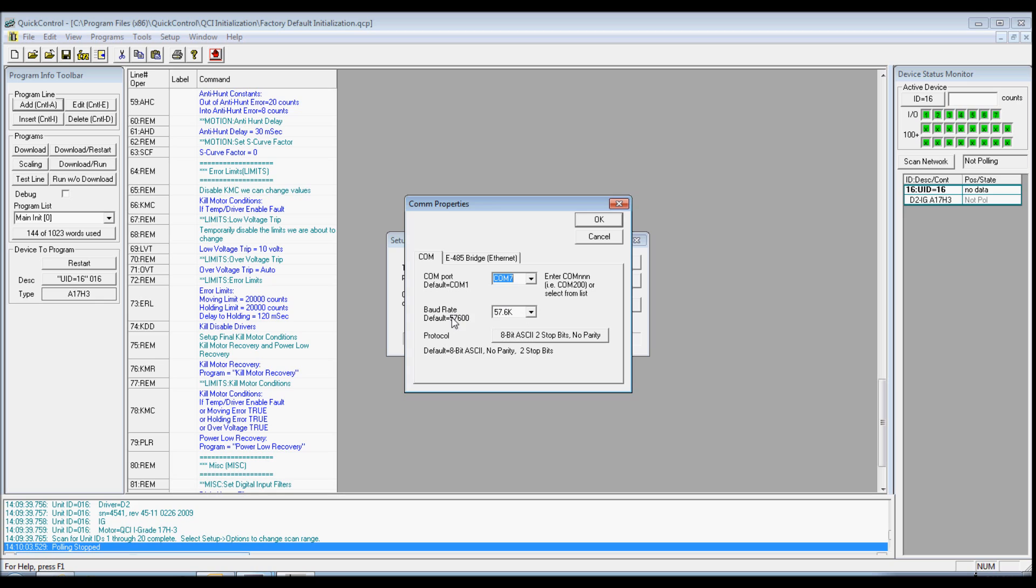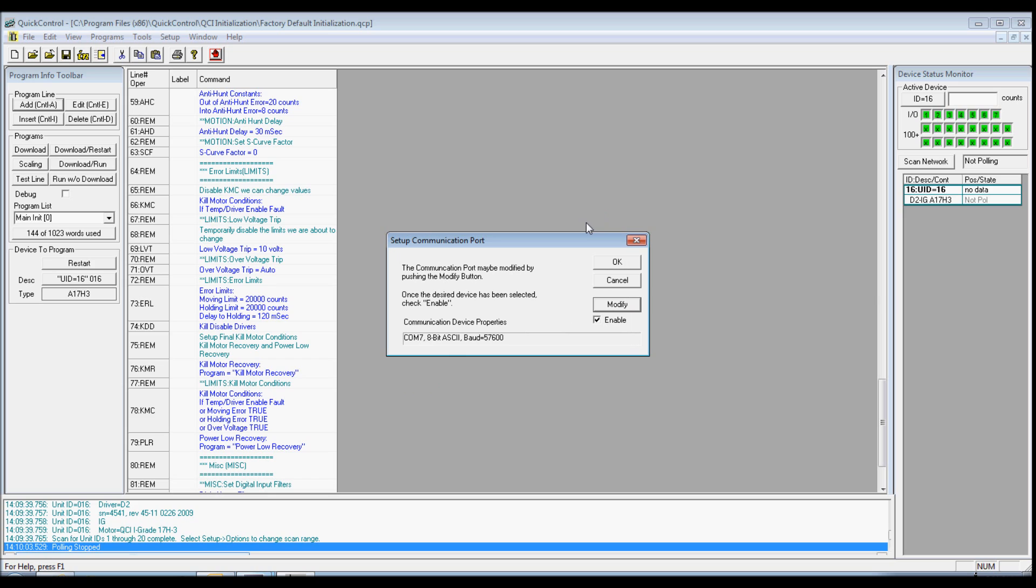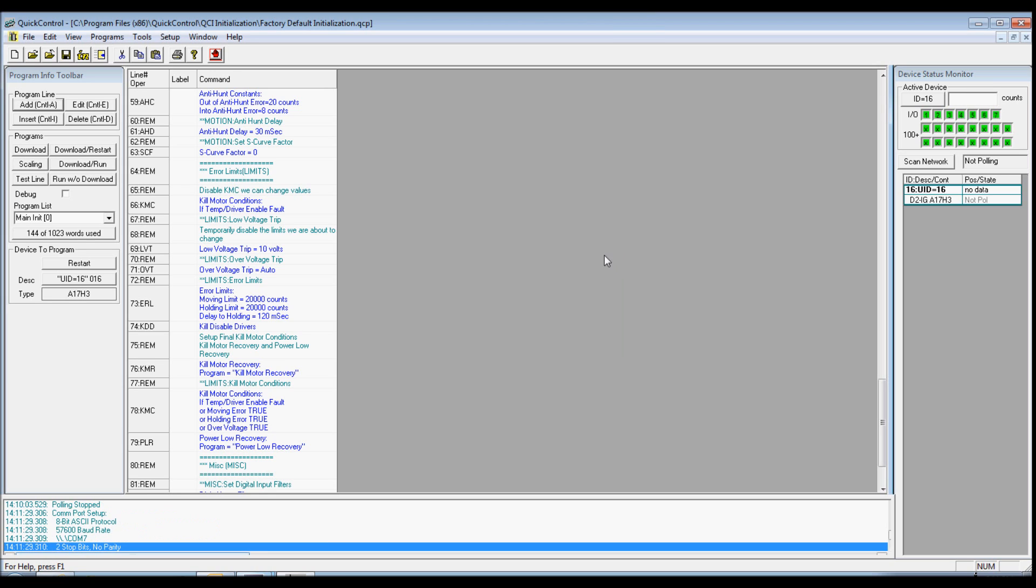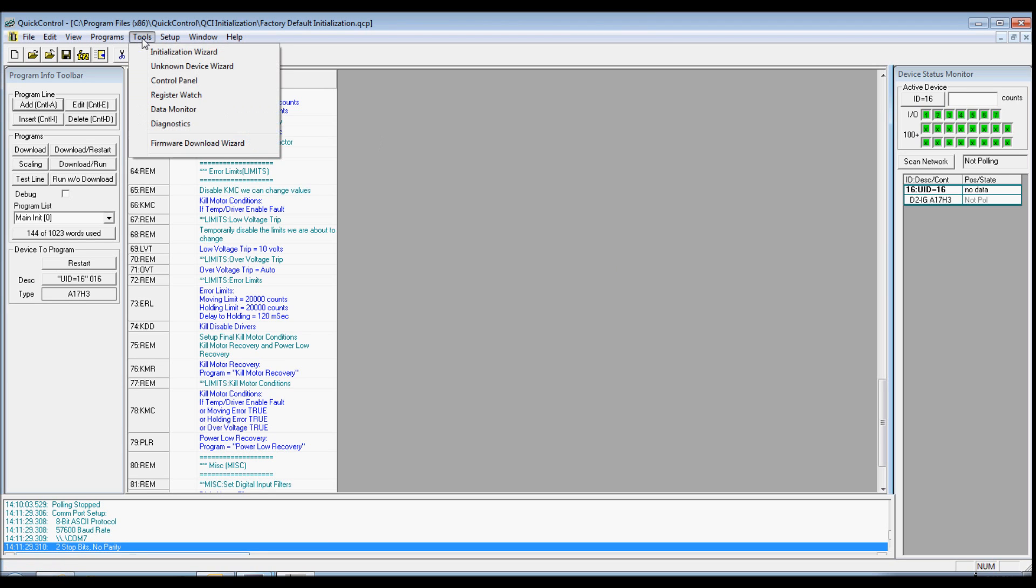You will want to set up the default baud rate and protocol. The baud rate default is 57,600, 8-bit ASCII, 2 stop bits, no parity for protocol default. Click OK and then verify the Enable check box is selected and press OK.